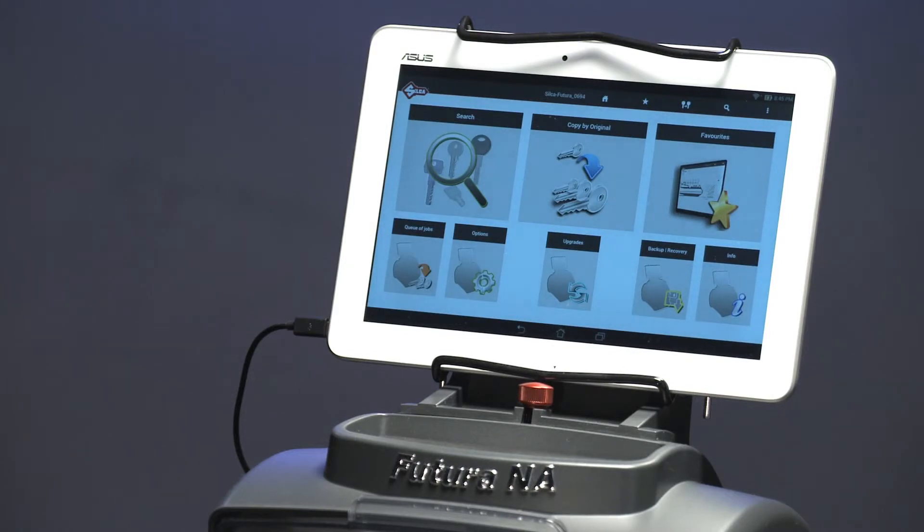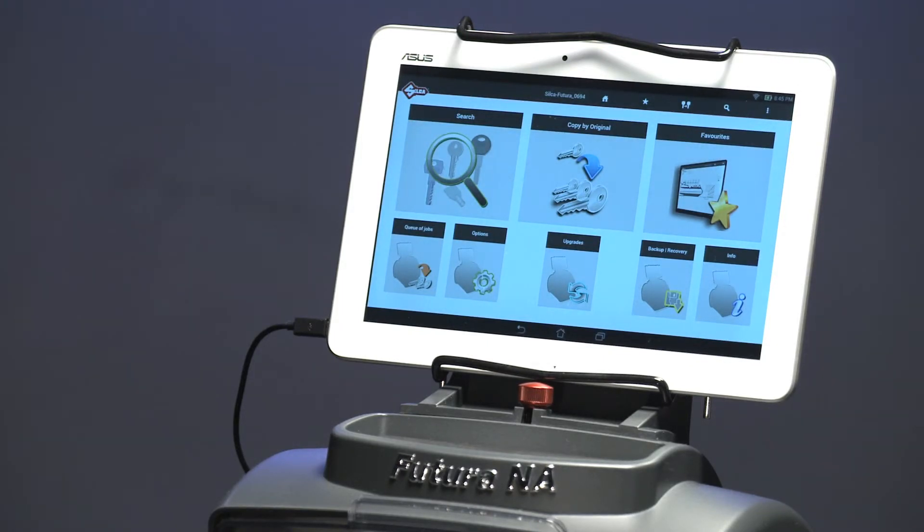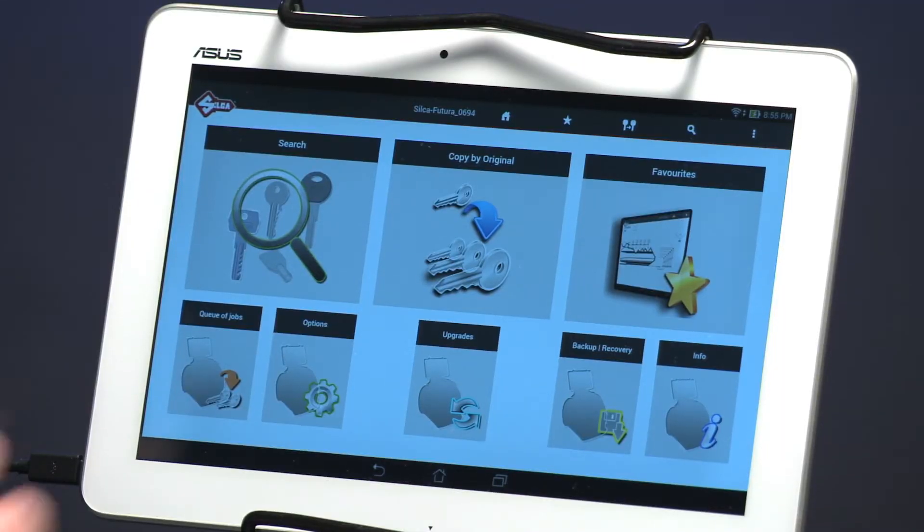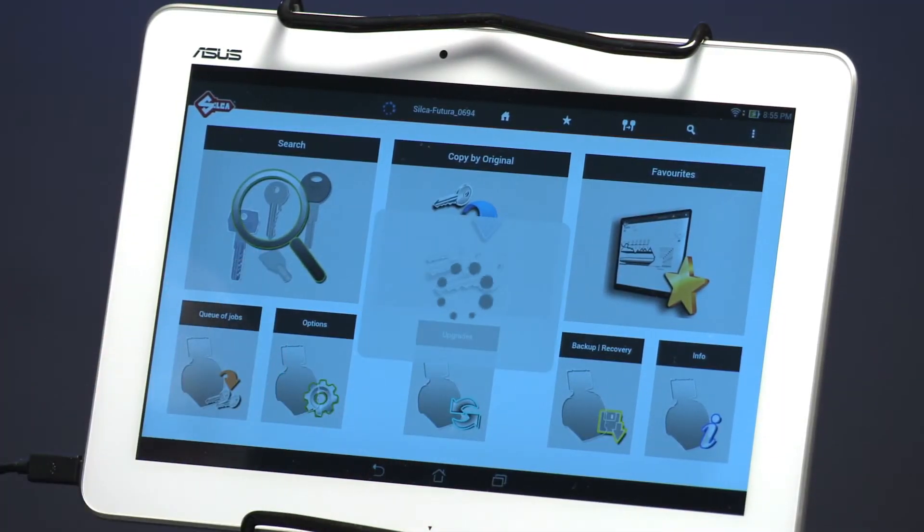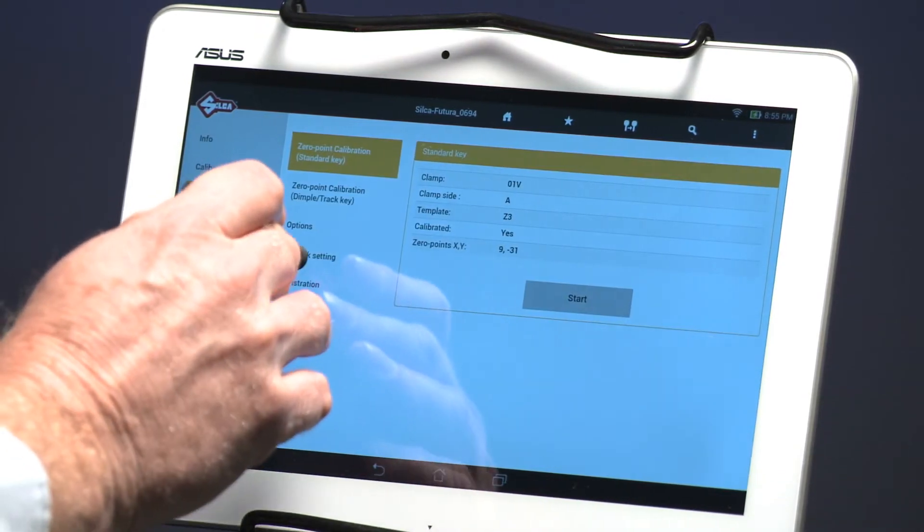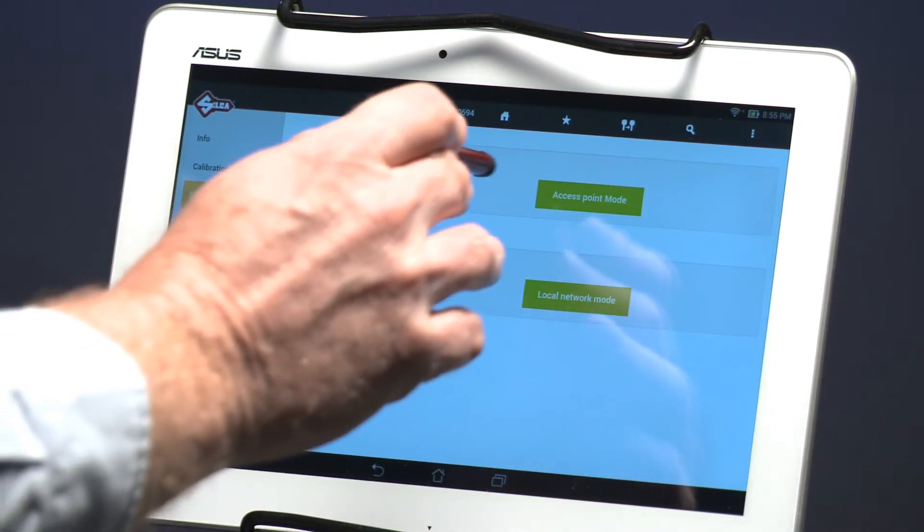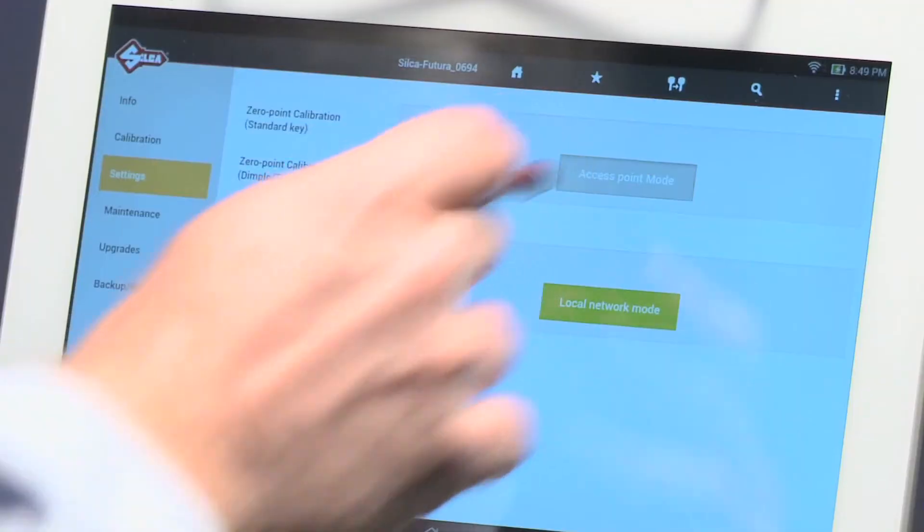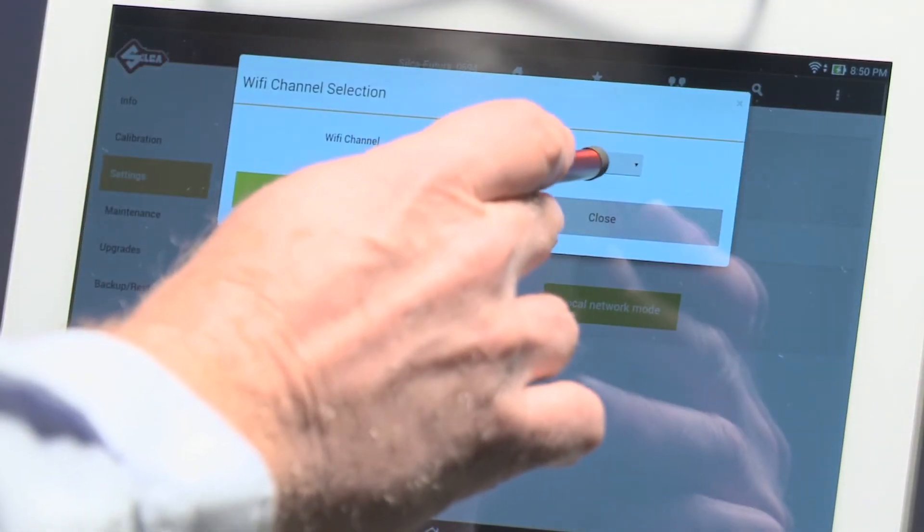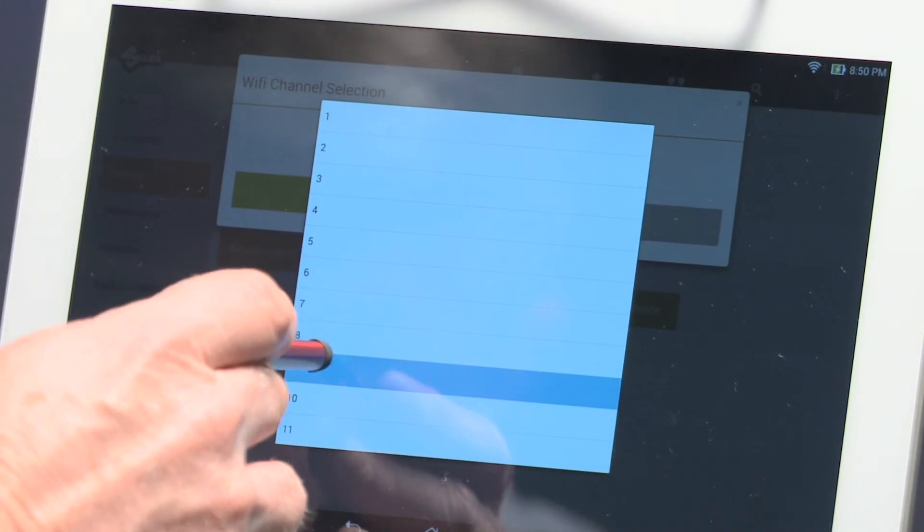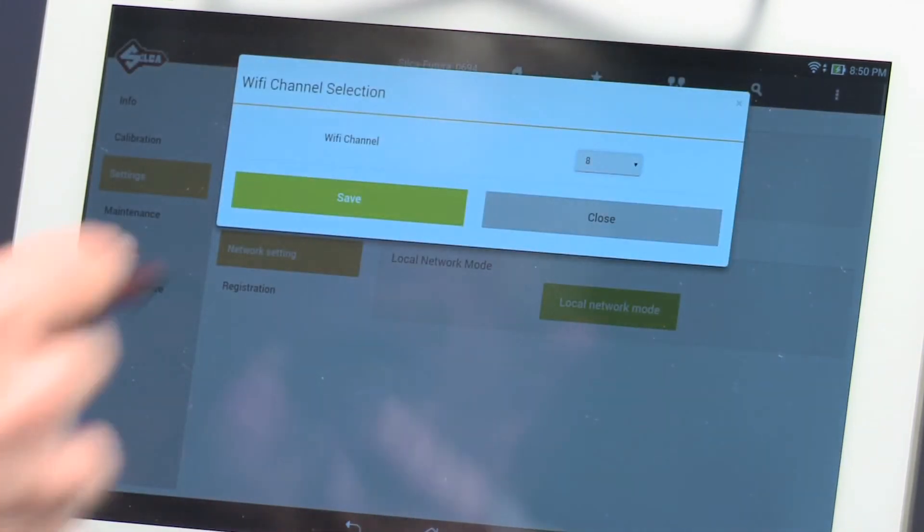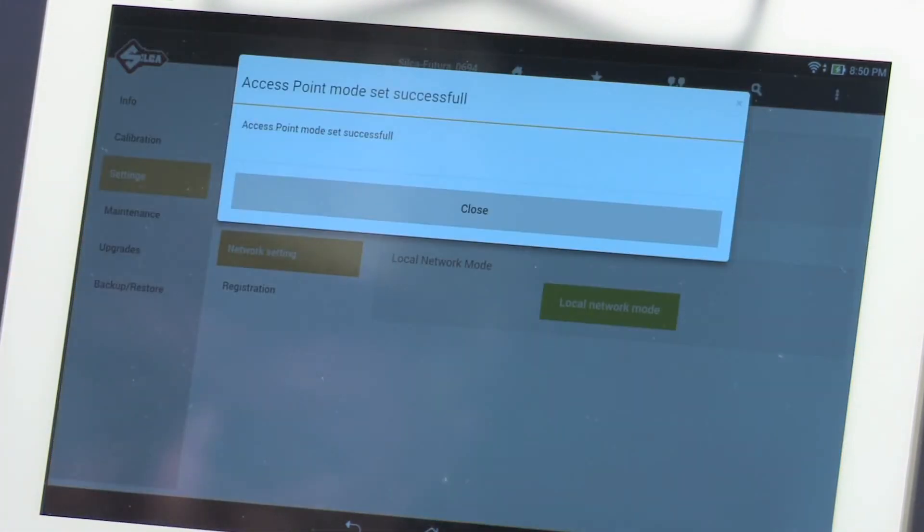If the area where you plan to operate the machine has several conflicting Wi-Fi signals causing abnormally long delays or difficulty connecting to the tablet, you can change the channel of the Futura signal for ease of connection. To change the channel, select Options, Network Setting, and then select Access Point Mode. Select the gray box showing Wi-Fi channels and select a different channel. Once saved, restart the machine and tablet to restore the connection.